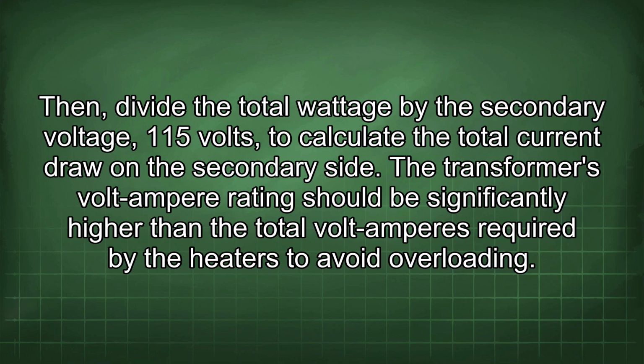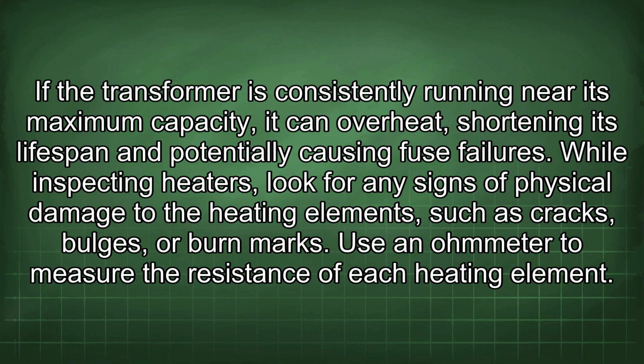The transformer's volt-ampere rating should be significantly higher than the total volt-amperes required by the heaters to avoid overloading. If the transformer is consistently running near its maximum capacity, it can overheat, shortening its lifespan and potentially causing fuse failures. While inspecting heaters, look for any signs of physical damage to the heating elements, such as cracks, bulges, or burn marks. Use an ohmmeter to measure the resistance of each heating element.